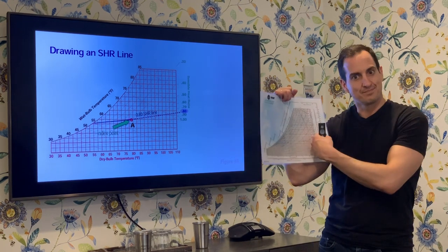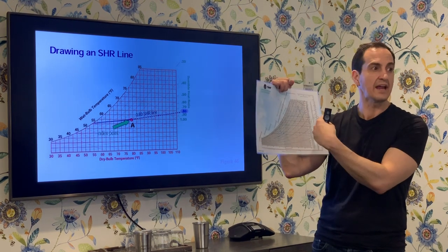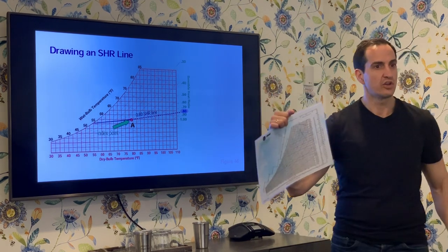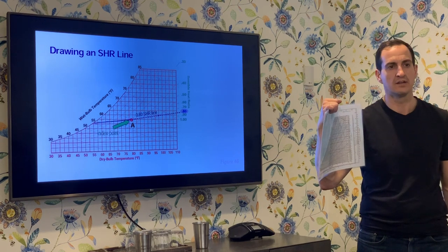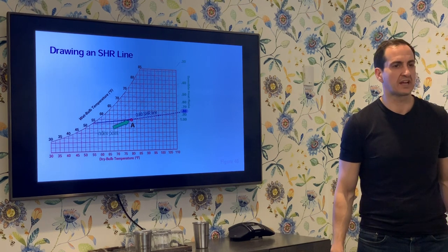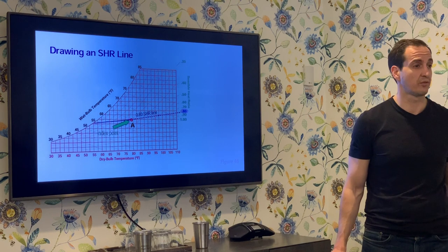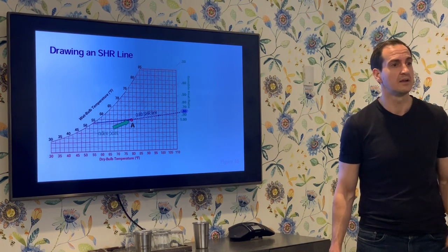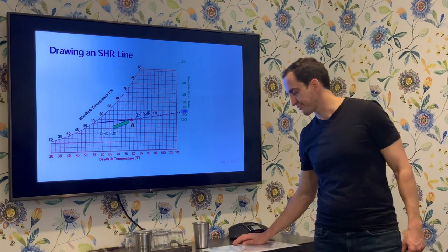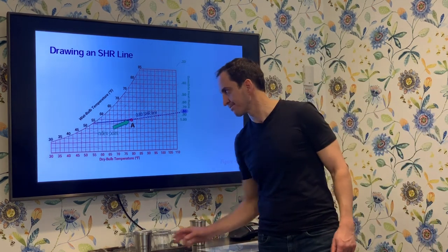The sensible heat ratio climbs quickly: anything below 0.8 or 0.75 means you've moved outside of comfort cooling into the world of commercial air conditioning for greenhouse and indoor grows. Steep curves are what we're looking for in grow rooms — we want to take a lot of water away without a lot of temperature change, meaning a lower sensible heat ratio.